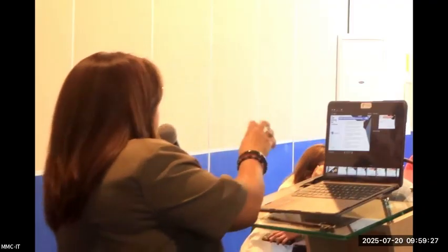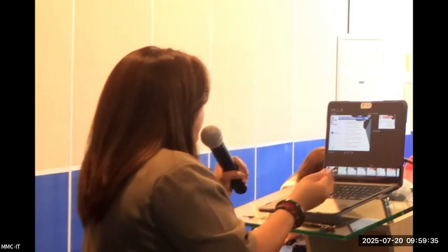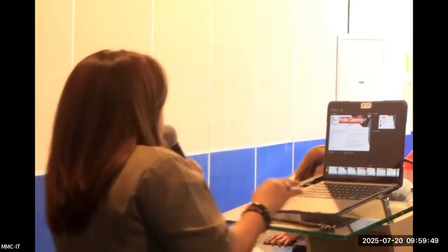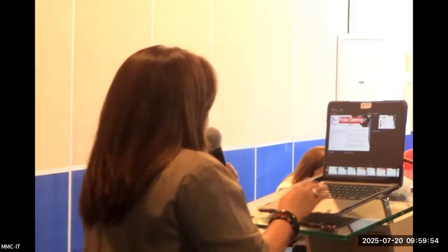Okay, so these are just some of the don'ts. Do not drop, do not dangle. When you have an open or cracked probe, do not put any water. Do not let your probe dangle loosely. Do not immerse your transducers deeper than the permissible level, and do not apply excessive bending or kinking. Okay, so why is there a need to clean our probes before and after using our ultrasound machine and the transducer?